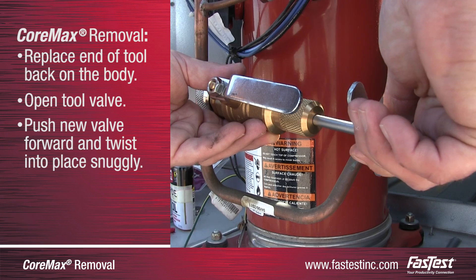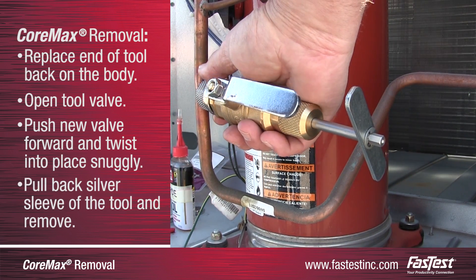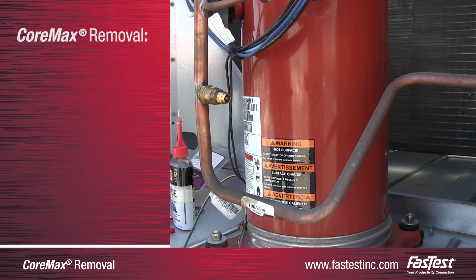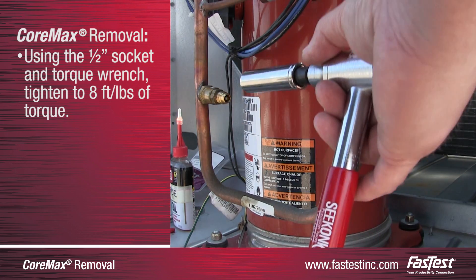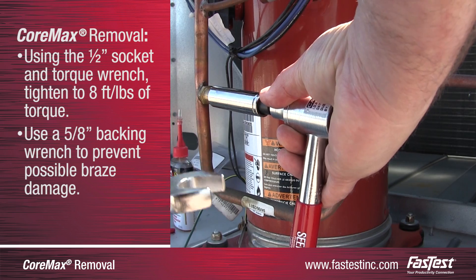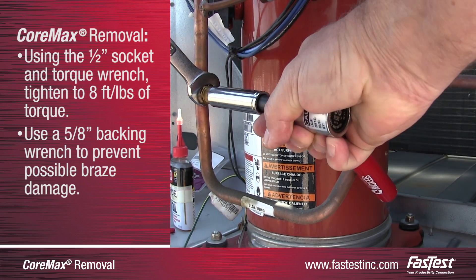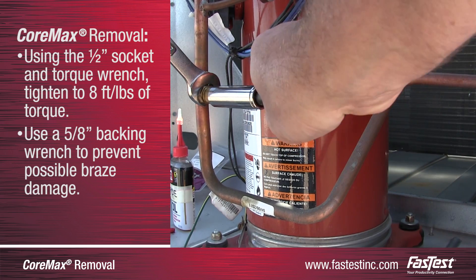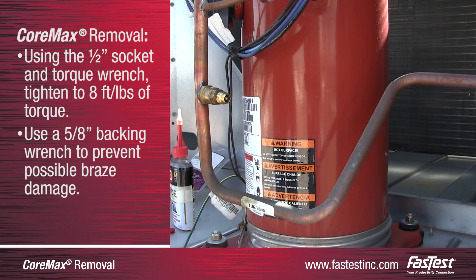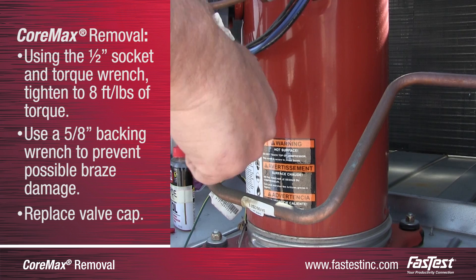Once the CoreMax valve has been completely inserted and hand tightened in place with the tool, pull back the silver sleeve to disconnect the removal tool from the new CoreMax access valve. To complete the replacement process, insert the exposed valve into the half-inch socket and torque wrench. Use a 5/8 inch backing wrench to hold the back of the CoreMax in place and prevent possible braze damage. Rotate the half-inch socket and torque wrench counterclockwise until tightened to 8 foot-pounds of torque, then remove the tools. Finally, replace the cap on the new valve.